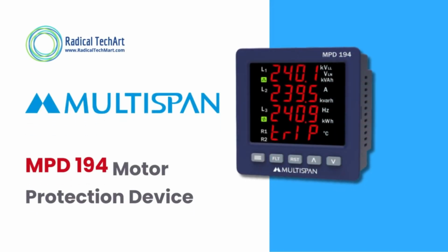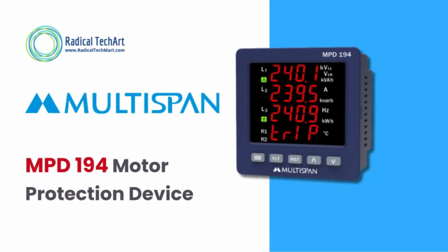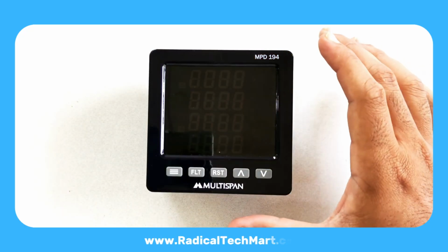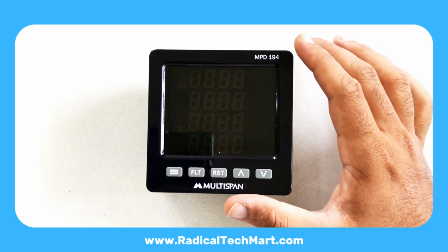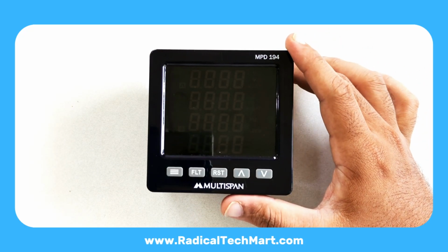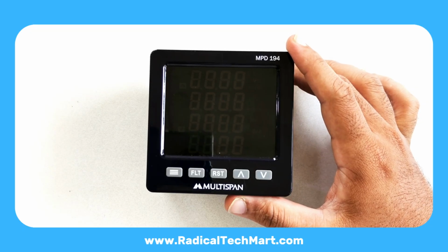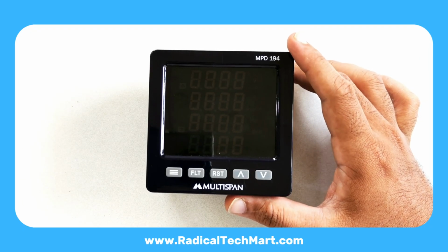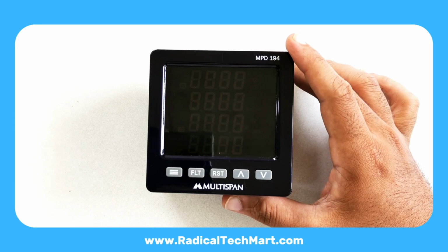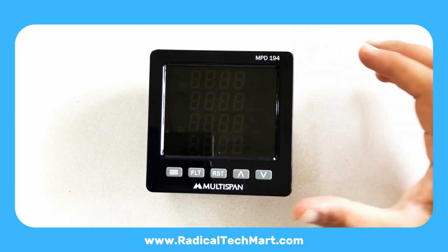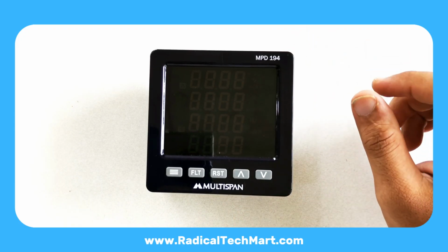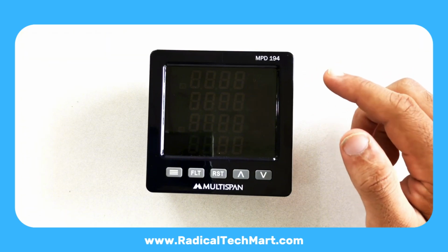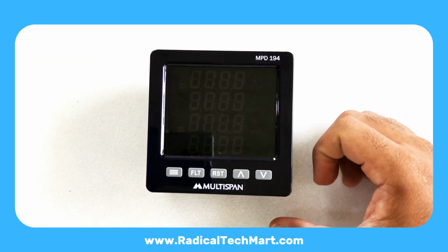Hello everyone. Today we have MPD-194, which is a motor protection device with both PTC input and CBCT, core balance CT, input. You can use this device as a motor protection relay and as a multifunction meter because it also shows kW, voltage, current, and frequency on the display.